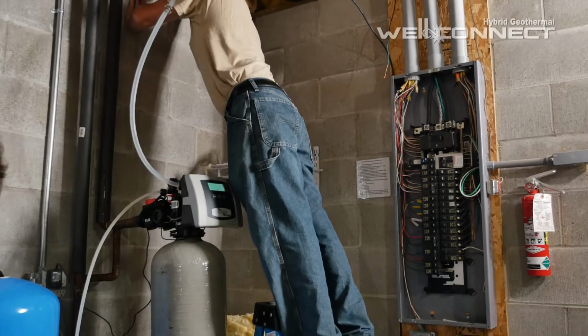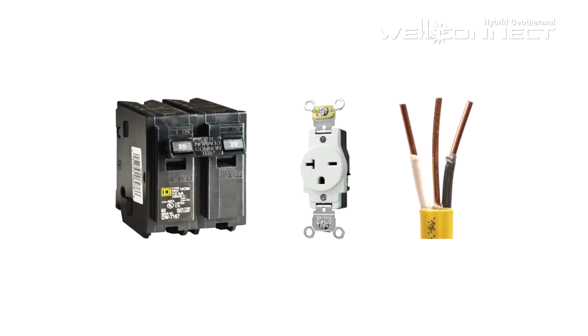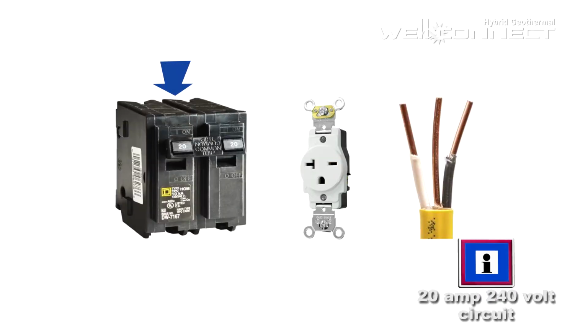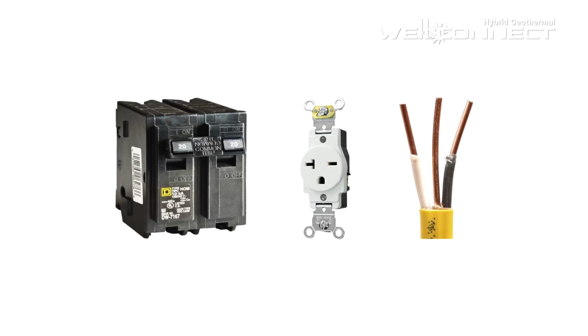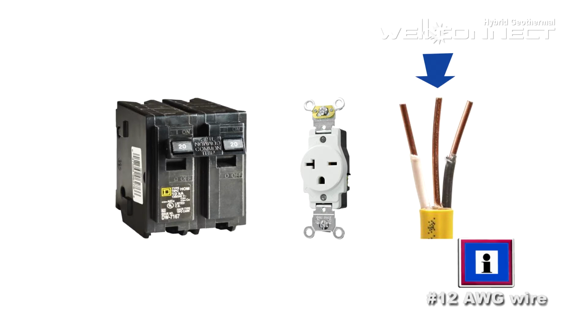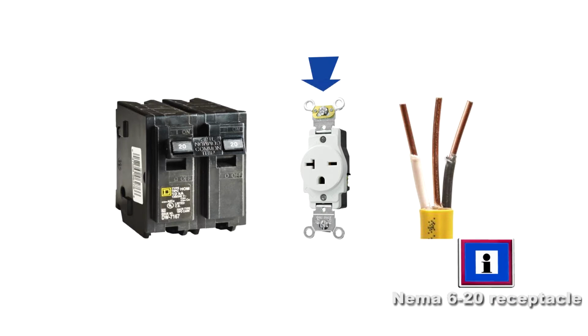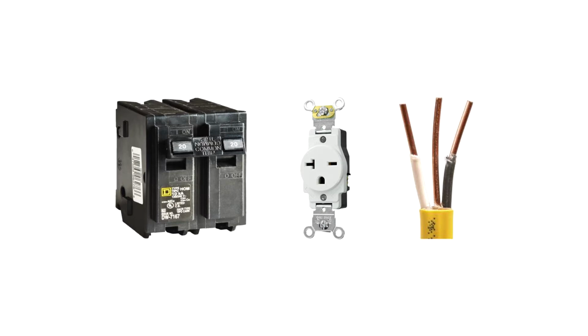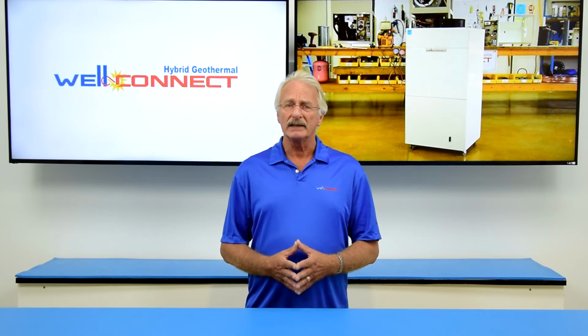To provide the required power supply for the WellConnect, an electrician should run a 20 amp, 240 volt circuit from the main service panel to a spot on a wall or post just behind the WellConnect. Number 12 AWG wire should be used, and the circuit should terminate with a NEMA 6-20 receptacle to receive the NEMA 6-20 plug on the WellConnect's 4-foot long power cord. Leave the circuit breaker for the WellConnect in the off position until the system is ready for startup.